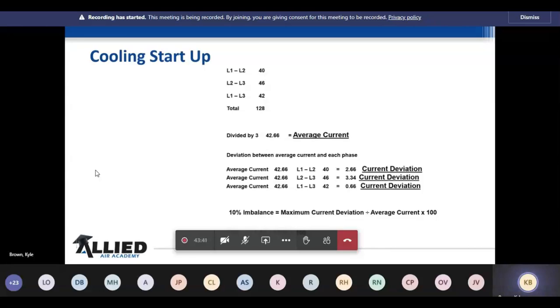Now the current imbalance simply means, usually if your voltage is way out of balance, this can be too. But if we go in and start adding accessories when it's on the roof, and we put too much on L1 and L2, you're going to get a current deviation or a current imbalance on that unit, and you can cause issues as well too. So if you look at this particular unit, again, we read L1 to L2, L2 to L3, and L1 to L3. So once you get used to doing this, it's not going to be much of an issue or a problem, but the mechanical contractors need to know this. We total it up, and then we divide by 3, and we got our average current. So our average current is 42.66 on this one. So we put it all in our formula, and you'll notice that only one really sticks out.